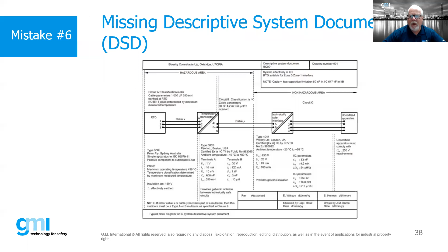So it gives us the information subject to the loop calculations, the components that are for use on the circuit, the wiring installation drawings, the cable lengths and/or types, the identification numbers, the date and name of the signature of the designer, and any analysis of a surge protected device. And again, the installation must match the DSD. So this is an important thing that people fail to remember. As I think I said at the very, very beginning, remember, intrinsic safety is a system concept.